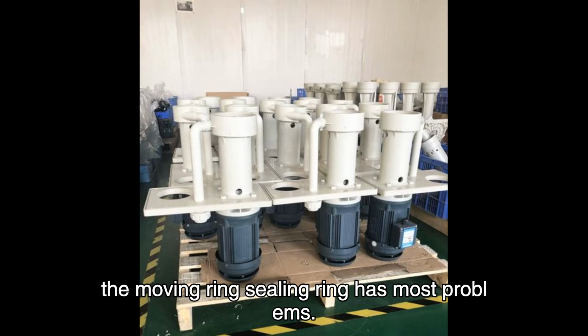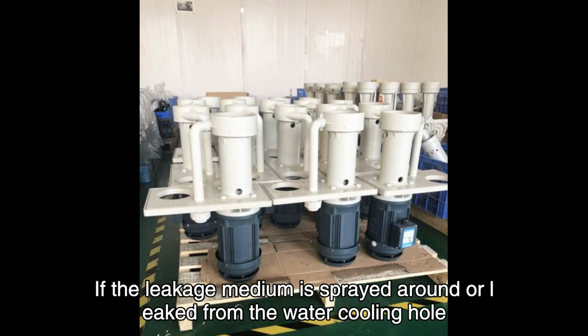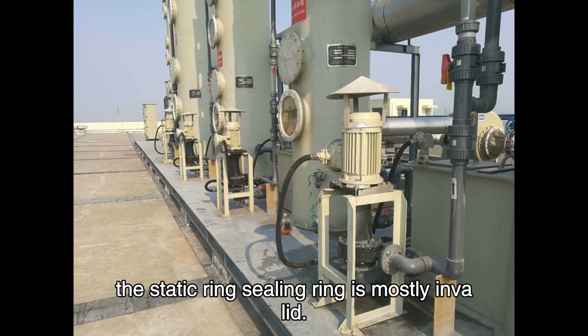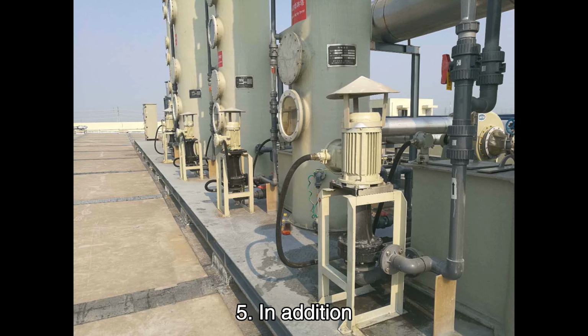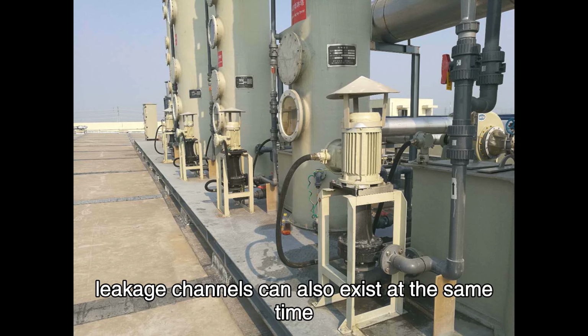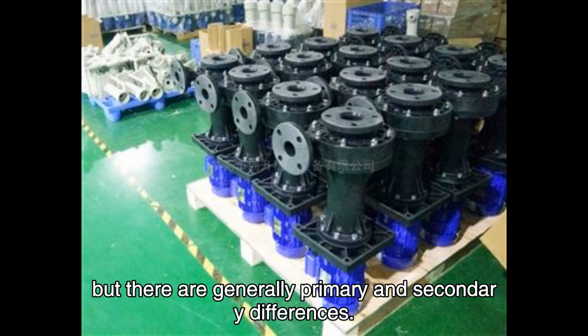4. If acid and alkali-resistant vertical pump leakage medium is spread along the axial direction, the moving ring sealing ring most likely has problems. If the leakage medium is sprayed around or leaks from the water cooling hole, the static ring sealing ring has mostly failed.